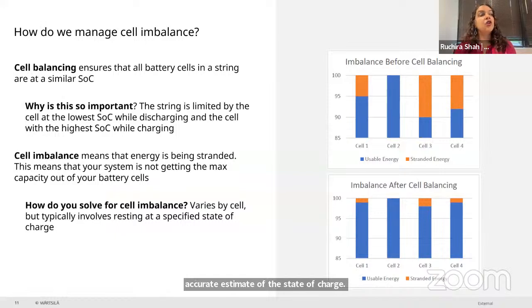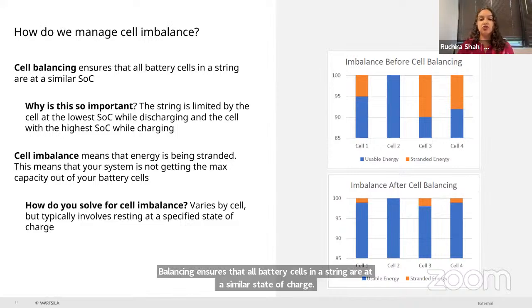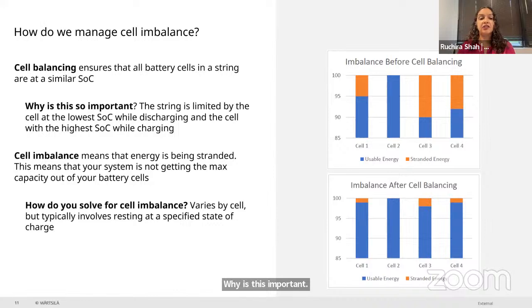Cell imbalance is another problem we see, similar to the state of charge calibration challenge. Cell balancing ensures that all battery cells in a string are at a similar state of charge. This is important because the string is limited by the cell at the lowest state of charge while discharging, and by the cell with the highest state of charge while charging.